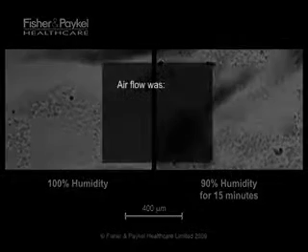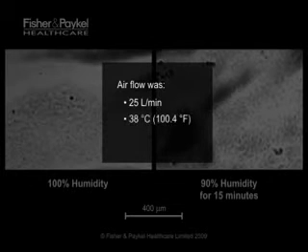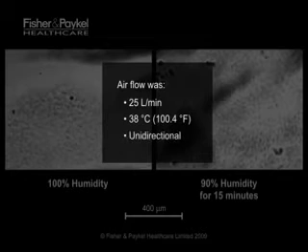For both recordings, the air was supplied at 25 liters per minute and 38 degrees Celsius from the humidifier. For simplicity, unidirectional airflow has been used in all the demonstrations. As we mentioned earlier, heat and water vapor are normally partially recovered during expiration.